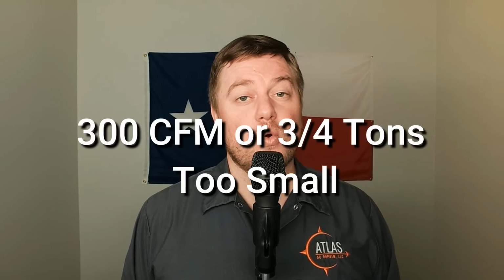After running a heat load calculation, we find that a properly sized AC for this house would be a 4-ton system, which makes sense since that's what you have now, and the last system is 20 years old. After diving into the ductwork, we find it's undersized by 300 CFM, or about 3/4 of a ton. Other than that, everything else looks good.